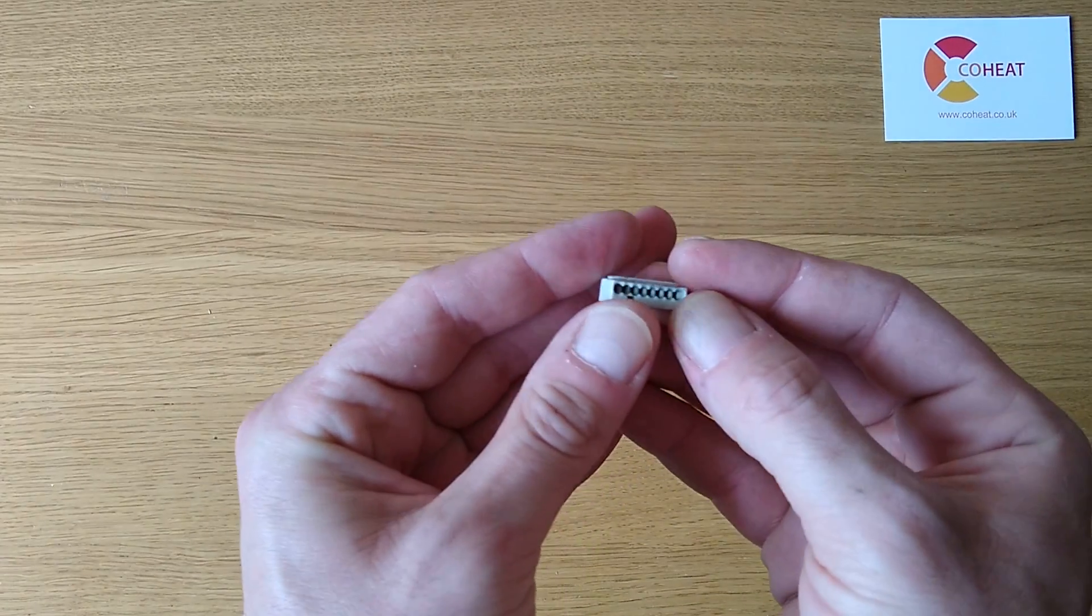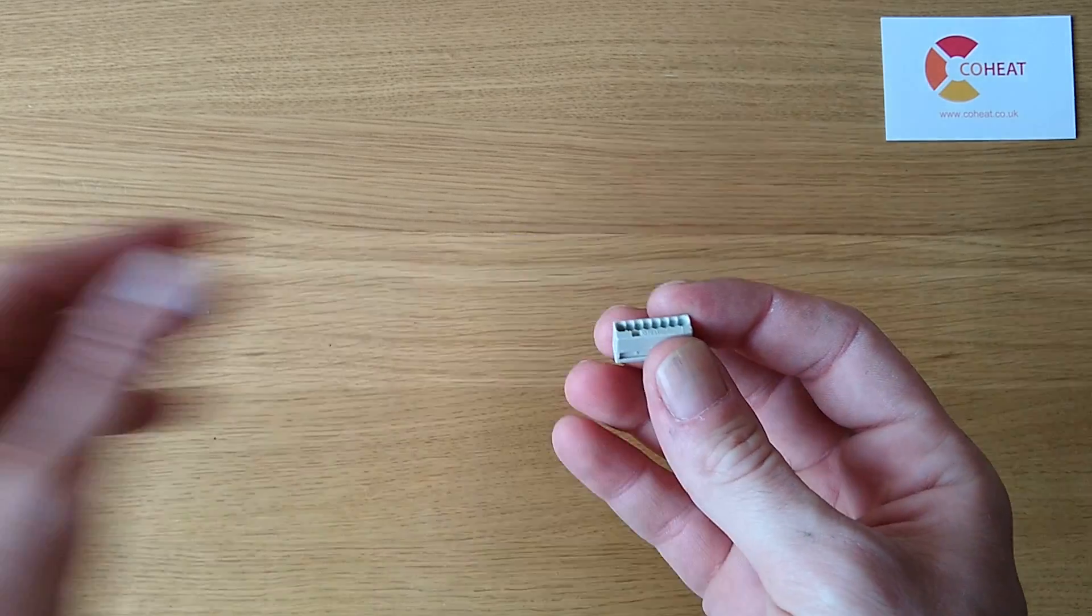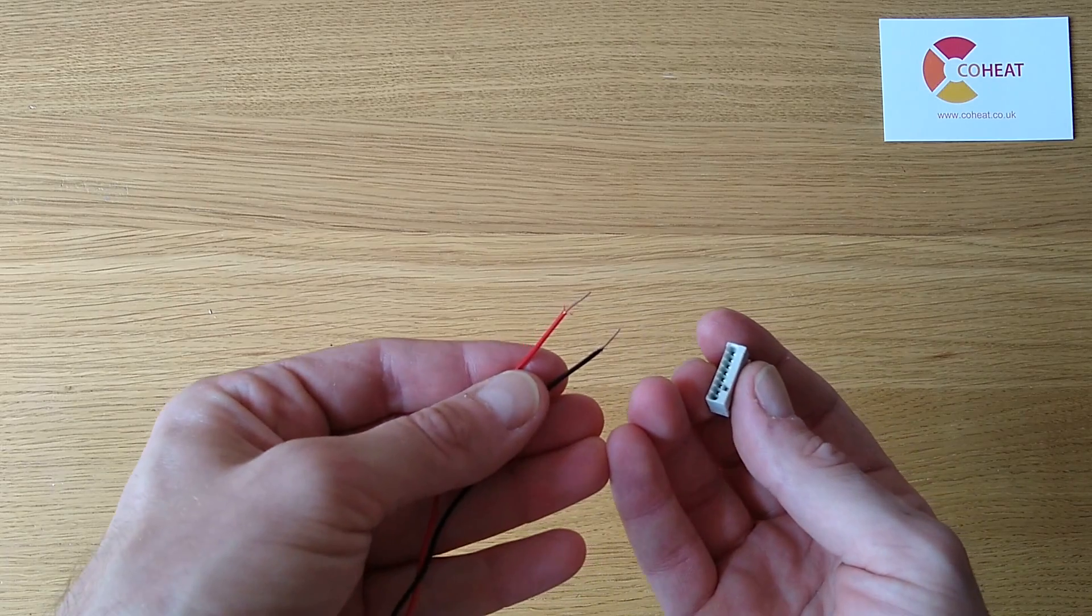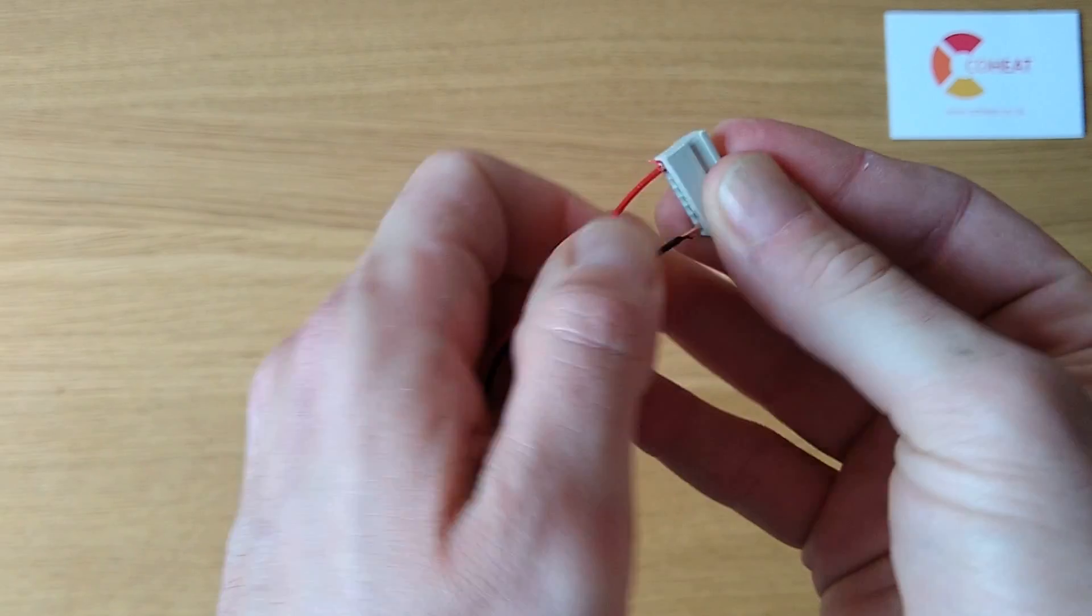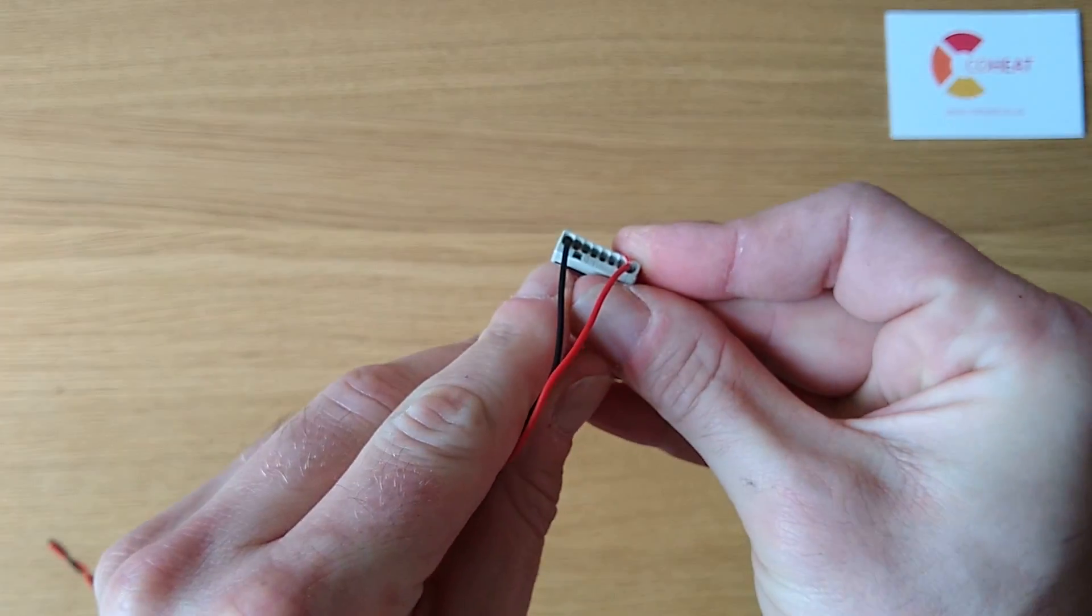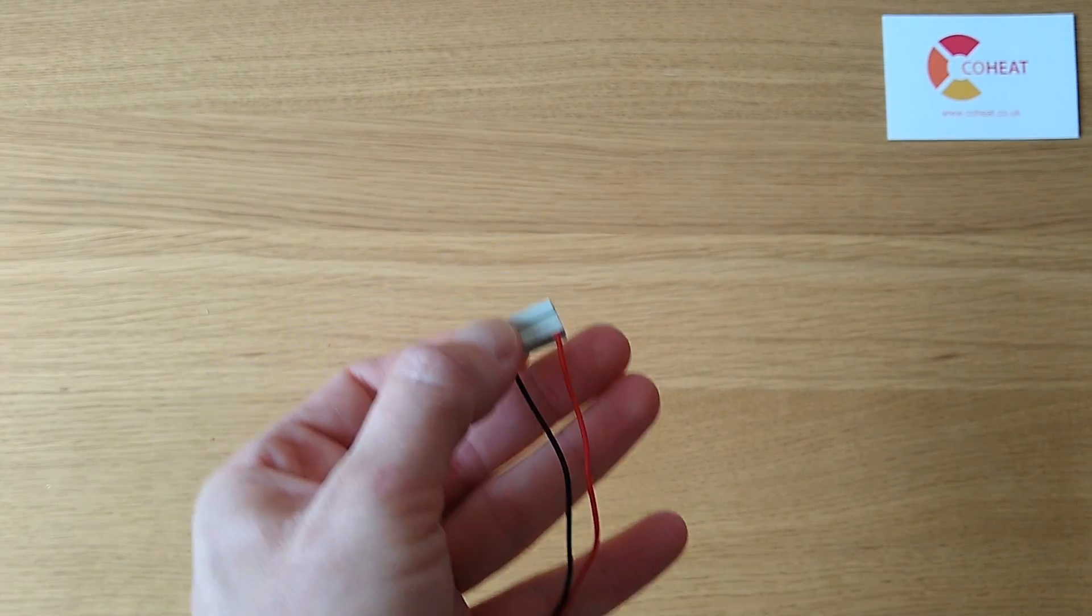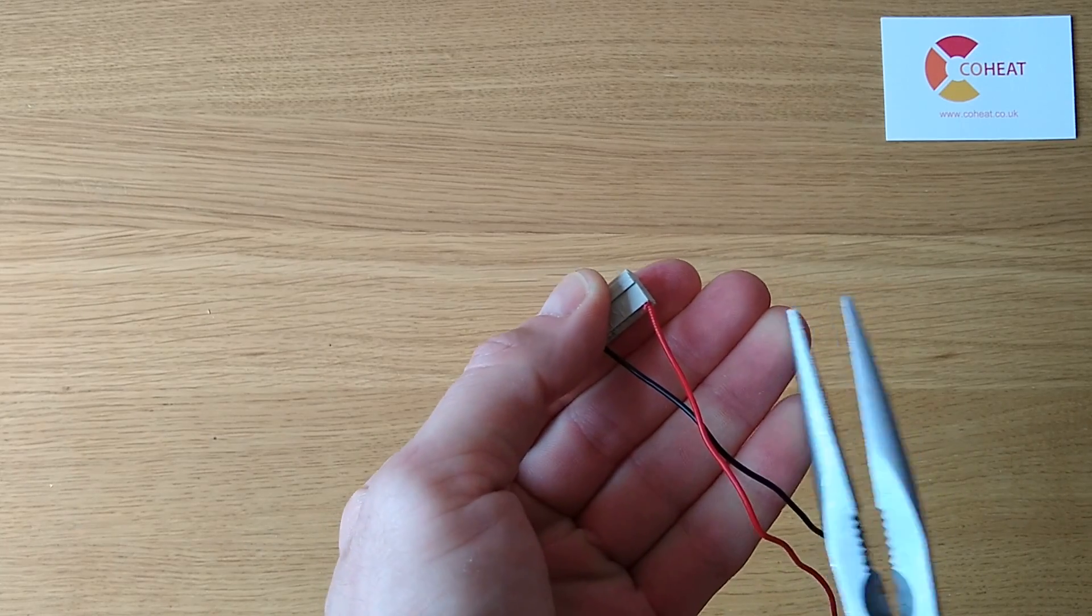There's also the KNX style connector, which is only suitable for use with KNX cable. You take your stripped KNX cable, about 8mm, and push it in. They have a test point built onto them, so you can use it for measuring voltages in the system. And if you need to remove a cable, you can grab it, and just twist and yank it out again, and back in.